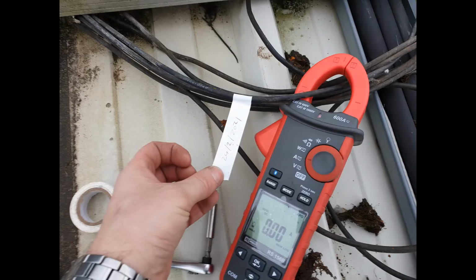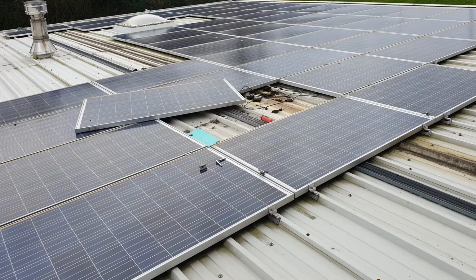You can get cable tracers for this application, and this would make things easier, but the method I use is to disconnect the faulty string, turn on the inverter, and trace which cables have no current. I label these and mark the date on so as not to mess up the next person, which could always be you.